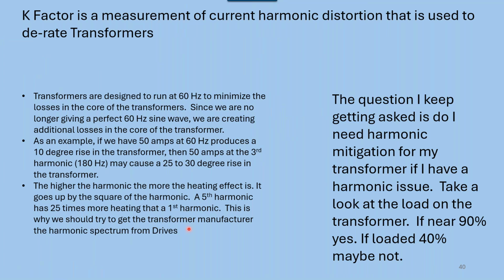So that's why we need to tell the drive manufacturers and the transformer manufacturers how much harmonics is in the system, okay? The question I keep getting is, do I need harmonic mitigation for my transformer if I have harmonics, or do I have a harmonic problem? I like to take a look at the load.